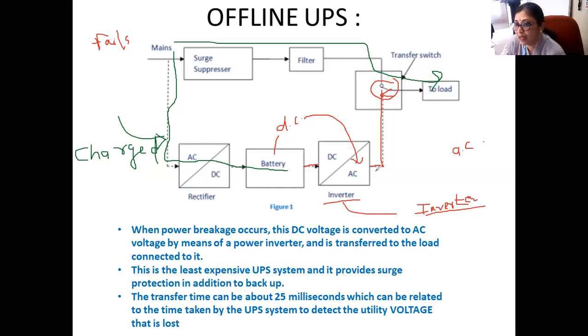This is offline because the load is connected to AC mains directly, and when the AC mains voltage fails, there is a switchover from mains voltage to the battery. This is called the transfer time - a finite amount of time required to switch the load from AC mains to the battery. This time, even though very small, of the order of 25 milliseconds, still exists.